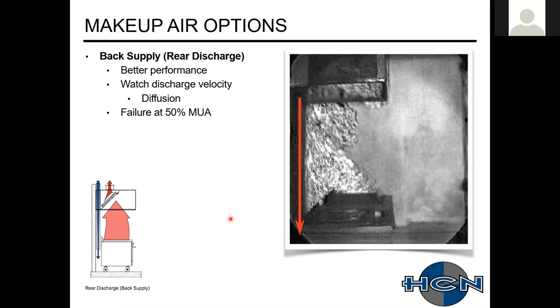Typically, that was the major problem I've seen with this: depending on the size of this back return, I think most standard sizes are usually 6 inches deep, or I've seen a little bit bigger. But the bigger you get, the better the system's going to perform, because you can put more air in there or a little bit less air and have less velocity. Nice thing about the back returns also is depending on where you're at, they provided another 6-8 inches. So your clearance to combustibles requirement could have been met by using a back return.